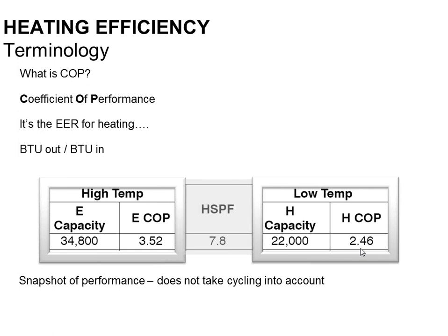We just look at the HSPF number, which kind of takes everything into account. However, it may be advantageous to look at COP when you're trying to compare an air source heat pump to a geothermal heat pump, because those products are not rated with HSPF. They are only rated with COP. Fortunately, the air source guys publish both, so you can make a comparison to geo if you want to, and we'll talk about that in a minute.